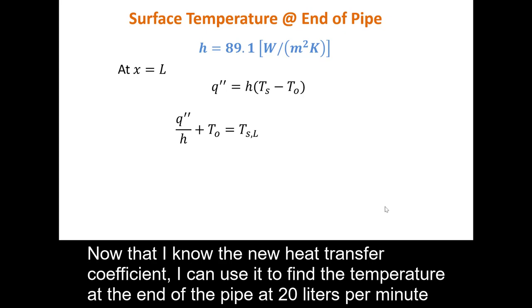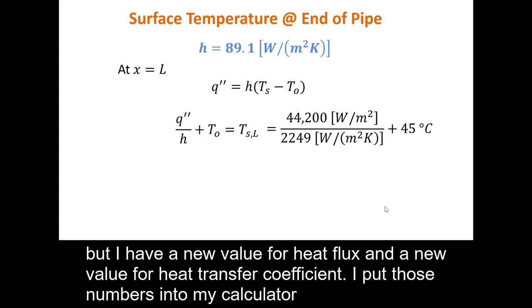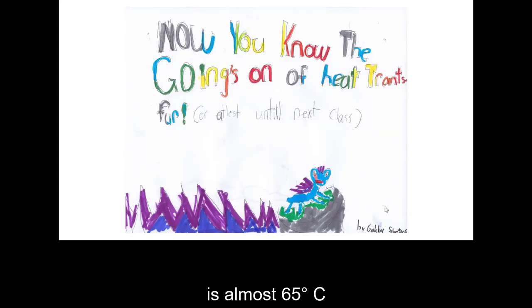Now that I have the new heat transfer coefficient, I can find the pipe surface temperature at the outlet at 20 liters per minute. The equation is symbolically the same as before, but with the new heat flux of 44,163 W/m² and the new heat transfer coefficient of 2,249 W/m²·K. Substituting these values, I find that the pipe surface temperature at the outlet is almost 65 degrees Celsius.